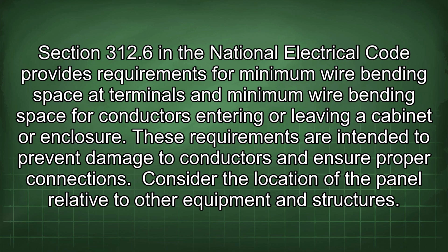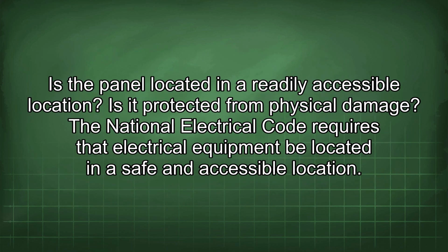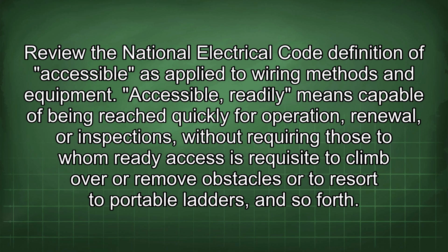Consider the location of the panel relative to other equipment and structures. Is the panel located in a readily accessible location? Is it protected from physical damage? The National Electrical Code requires that electrical equipment be located in a safe and accessible location. Review the National Electrical Code definition of accessible as applied to wiring methods and equipment. Accessible, readily, means capable of being reached quickly for operation, renewal, or inspections, without requiring those to whom ready access is requisite to climb over or remove obstacles or to resort to portable ladders, and so forth.